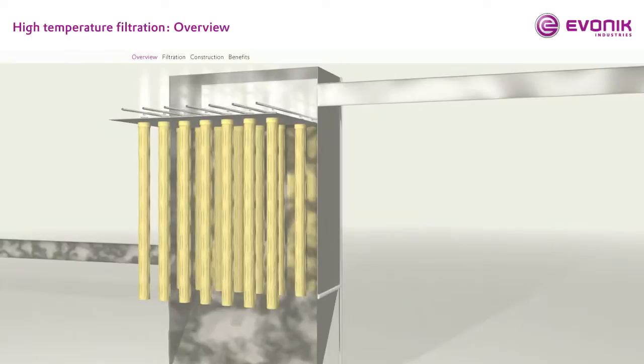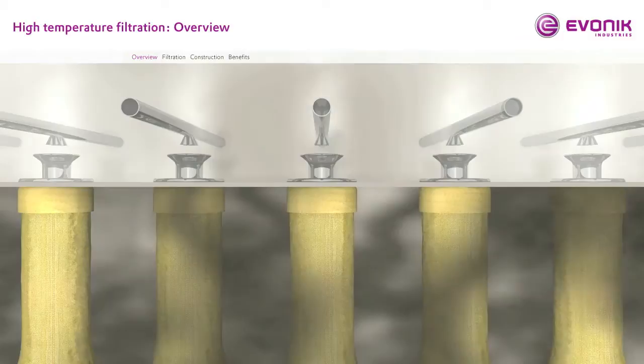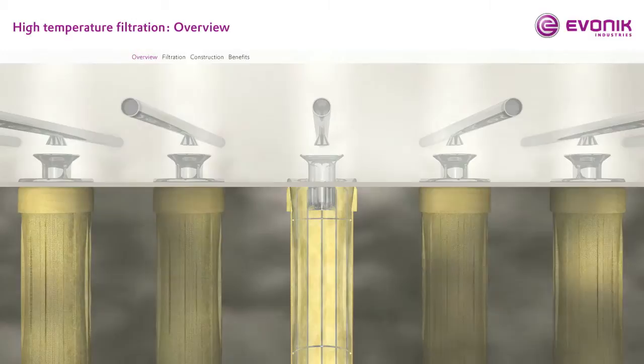A bag filter unit is a highly efficient tool for removing dust from gas streams. It is equipped with cylindrically shaped P84 polyimide filter bags. These bags separate the dust from the gas and ensure low emissions of particulate matter. During the filtration process, dust accumulates on the bags. A pulse jet of pressurized air then cleans the bags in a regular cycle in order to remove the dust cake and to lower the pressure drop.